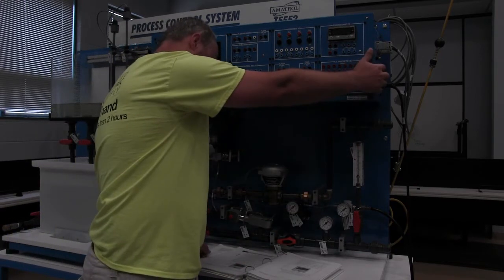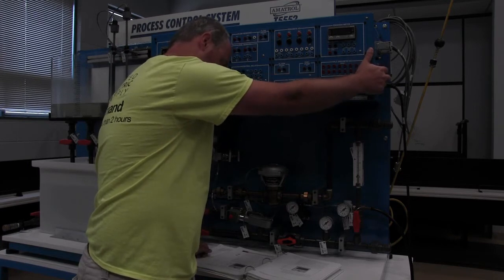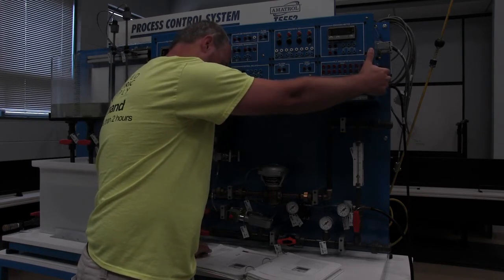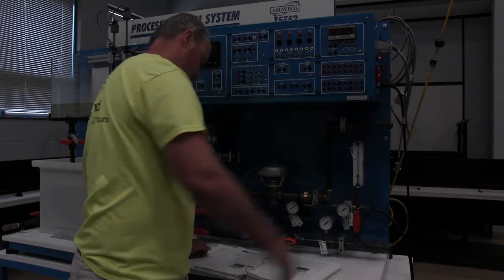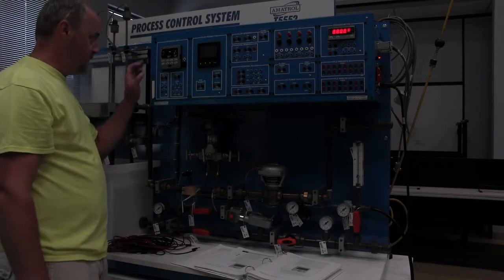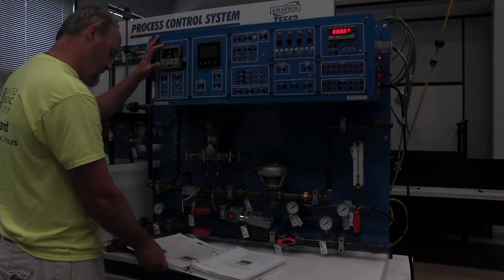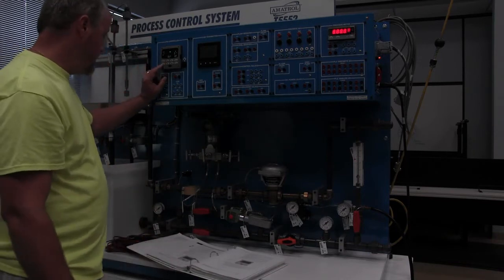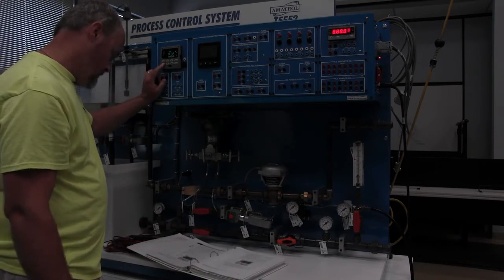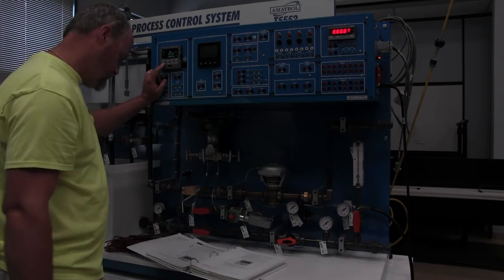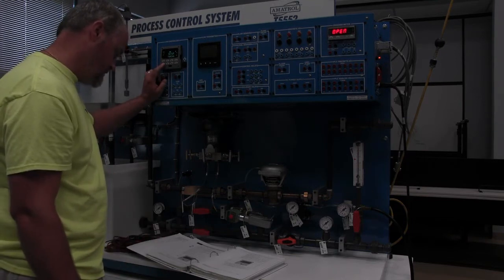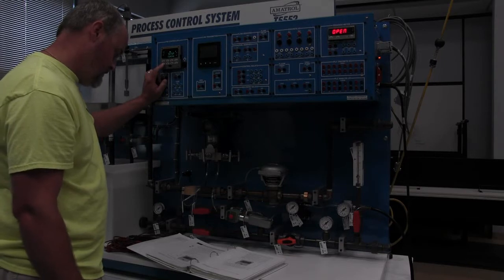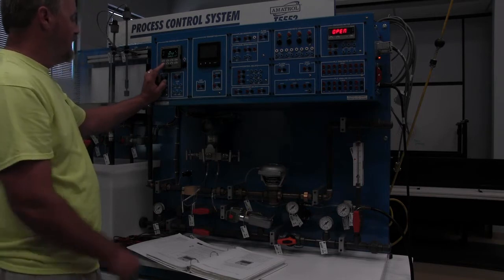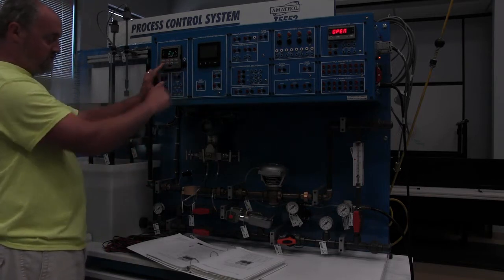Alright, so the next one says change the Honeywell UDC 3500 loop controller parameters. So we're going to be turning the power on. We're going to wait for test done. Once the test is done, we're going to press the setup key. We're going to press the setup key repeatedly to scroll through the parameter group until you come to input 1 parameter. So we're going to push the setup key. As we're pushing it, the lower section is changing. So now we're at input 1.